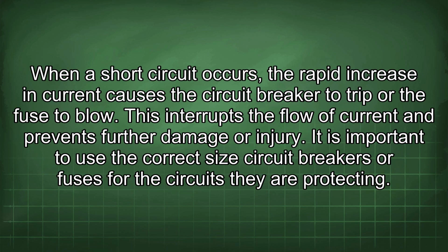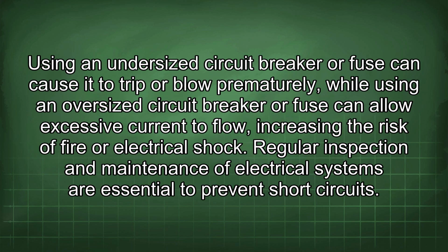When a short circuit occurs, the rapid increase in current causes the circuit breaker to trip or the fuse to blow. This interrupts the flow of current and prevents further damage or injury. It is important to use the correct size circuit breakers or fuses for the circuits they are protecting. Using an undersized circuit breaker or fuse can cause it to trip or blow prematurely, while using an oversized circuit breaker or fuse can allow excessive current to flow, increasing the risk of fire or electrical shock.